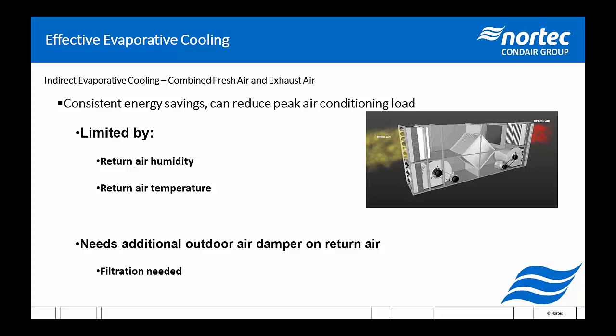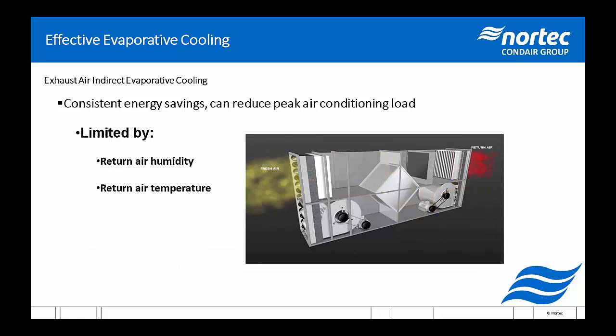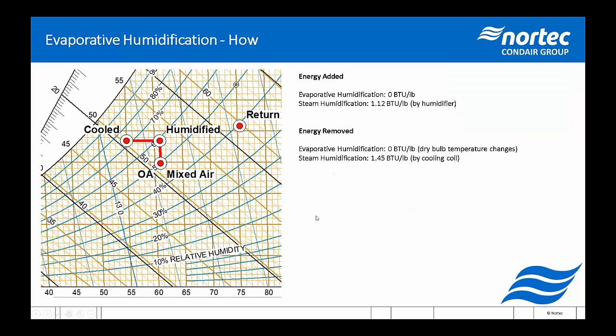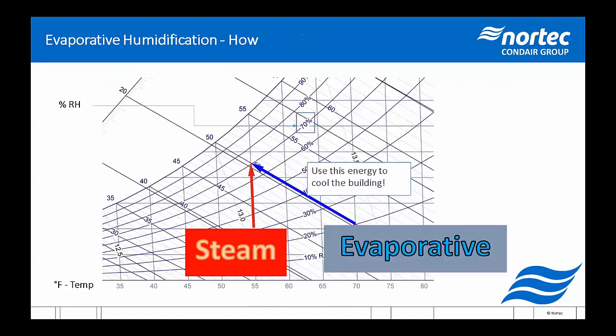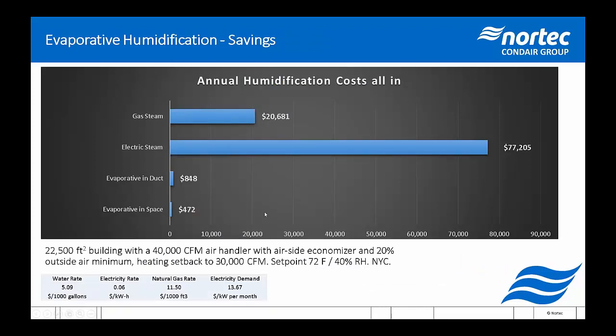So there was a good question that I should have answered earlier on the annual cost based on how many hours or pounds. I'm going to skip back to it before I forget. So the pounds per hour, which I now realize I didn't actually put on this, was somewhere in the range of 550 pounds per hour, and it was a 24/7 system that allowed the humidity in the space to creep up to around 50% for cooling and stayed at 40% for the gas steam and the electric steam systems. In New York City, for a 24/7 system that requires 40% year-round, I believe we're looking at around 3,300 or 3,400 hours a year of the humidifier operating at some percentage.